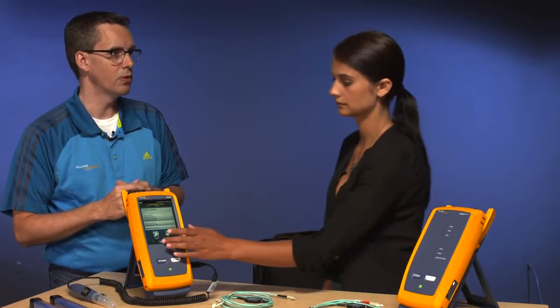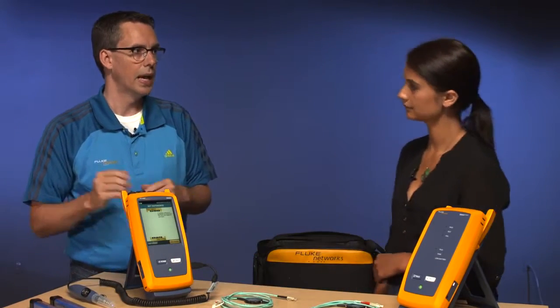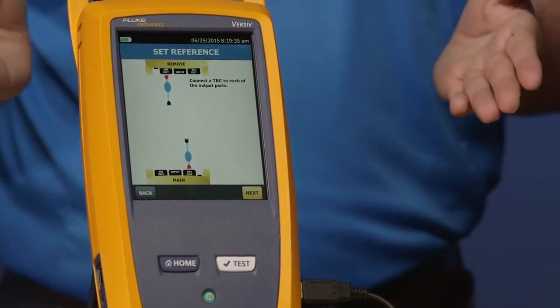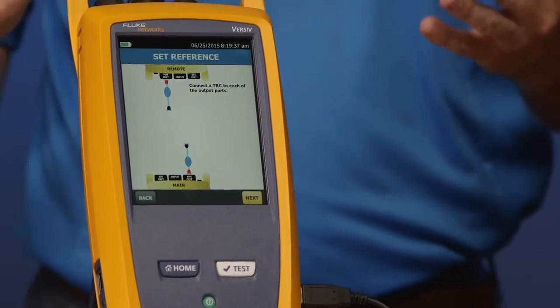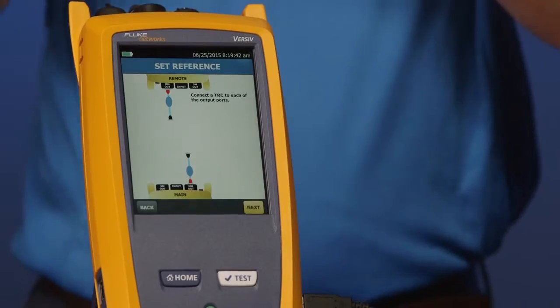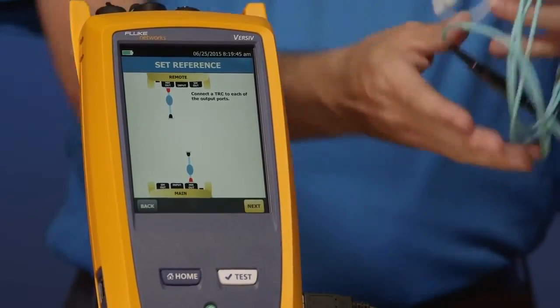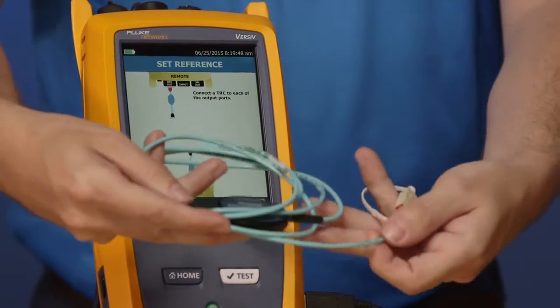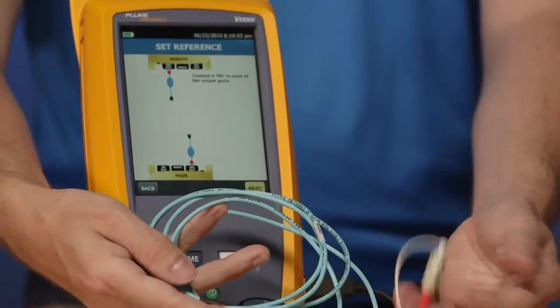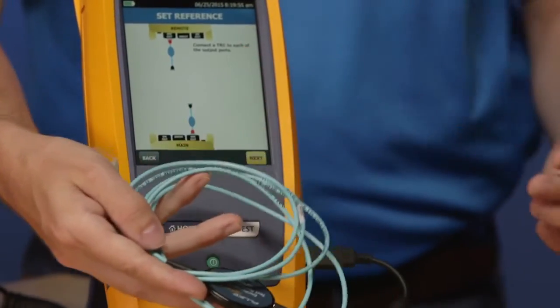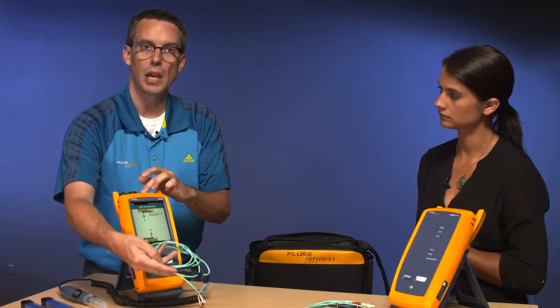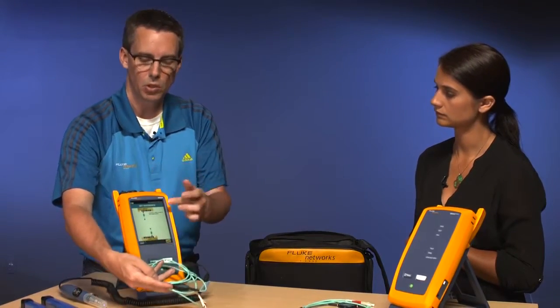Go ahead and tap 'set reference' and we'll run the wizard. The first thing it does is tell you — you can see on the animation — to connect the cords to the output ports. You'll see the little puck on the drawing. We've got a 50-50 chance of getting the cord the right way around, and it does actually matter. One end is red, the other is black. Red is hot, black is cold — so red connects to the output port on the instrument.